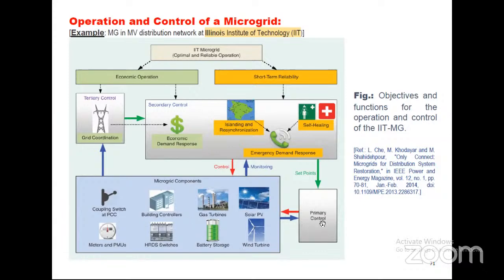So here you can find there is a primary control, a secondary control, and a tertiary control. It is similar to the previous tables we have discussed: primary is at the microgrid level, secondary is between the layer of primary and tertiary, and tertiary is between microgrid and grid. So if we are talking specifically about this successful example of the Illinois Institute of Technology microgrid, it has a coupling switch at the point of common coupling, which is making the control. It is collecting data using meters and PMUs. It has building controllers in different buildings of the institute. It has HRDS switches, battery storage, wind turbines, solar PV, and gas turbines as distributed generation sources of electricity at different locations within the campus, right?